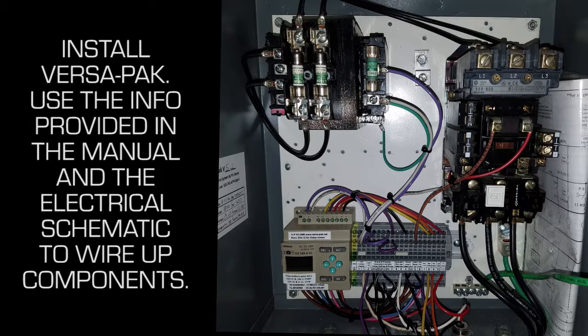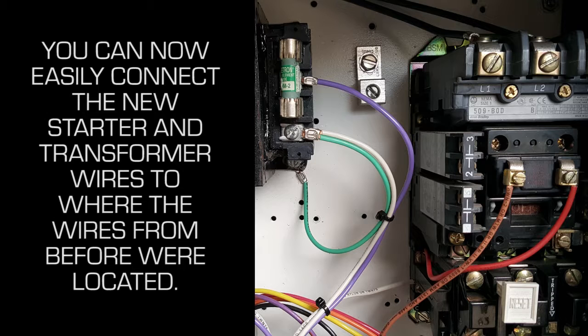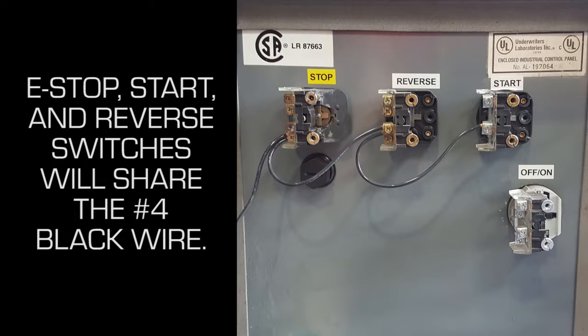Install VersaPack. Use the info provided in the manual and the electrical schematic to wire up components. You can now easily connect the new starter and transformer wires to where the wires from before were located. E-stop, start, and reverse switches will share the number 4 black wire.